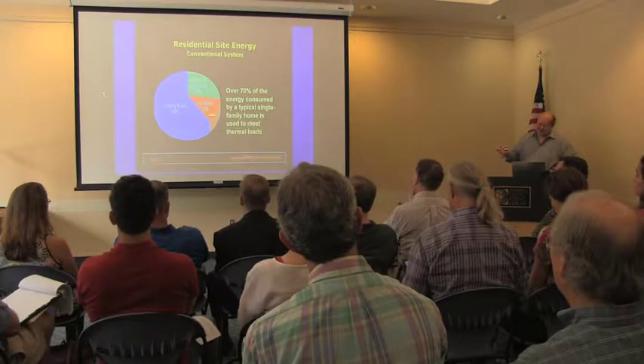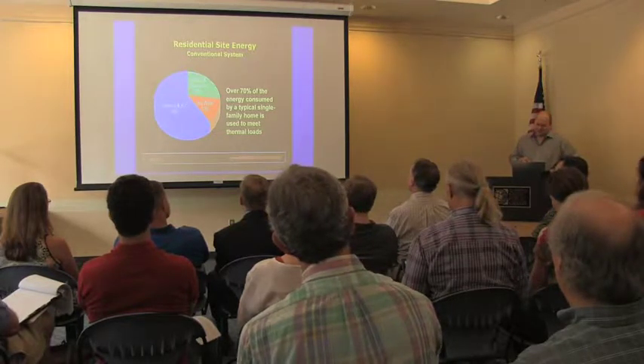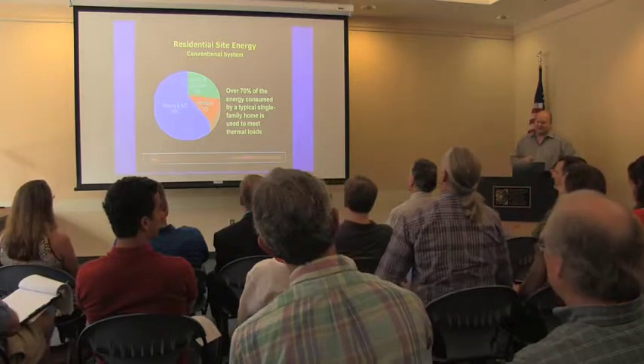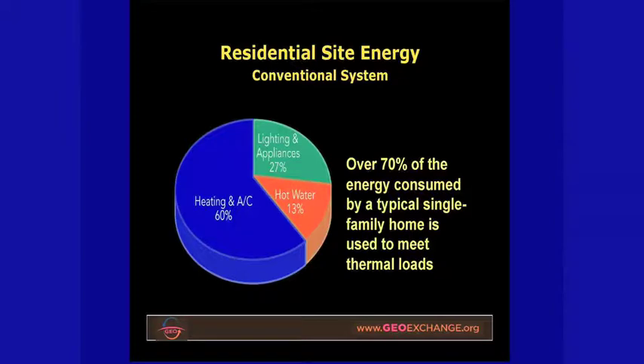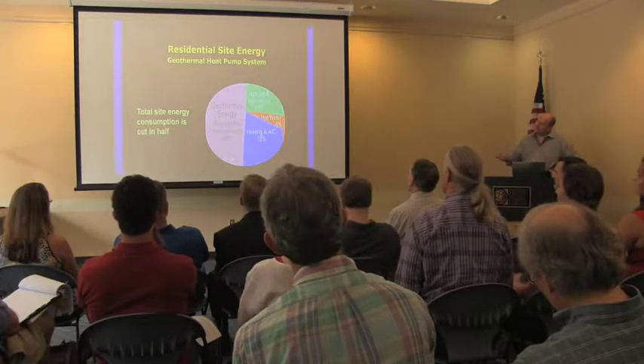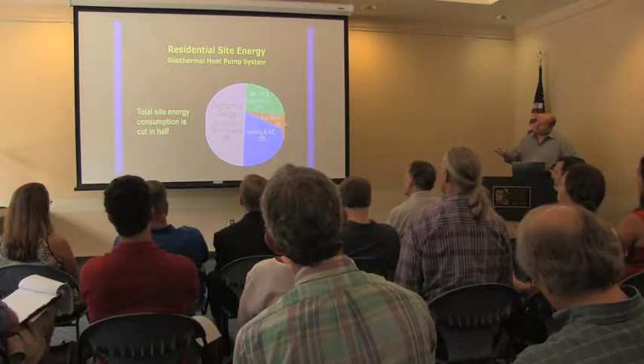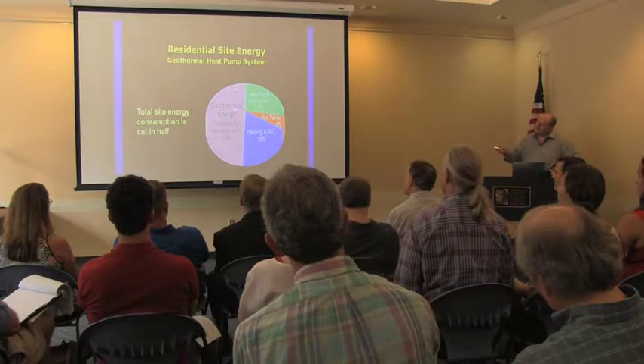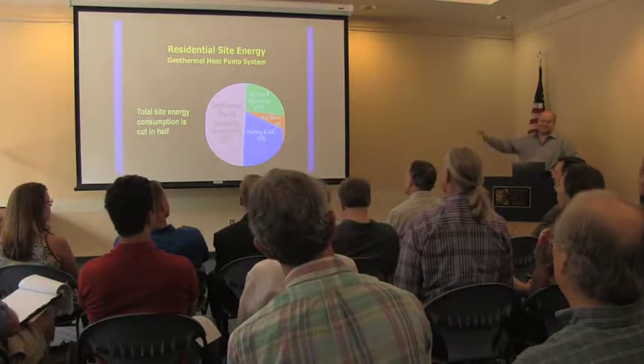So we essentially usually design our systems to make about 100 degrees of temperature coming out of the registers. I guarantee you, it heats your entire house when you're on. So this becomes important because if you understand that about 3/4 of the entire energy to heat a house goes into heating and cooling and hot water, that is a significant amount. The light bulbs and the appliances and the TVs and everything else, that's just a minor portion of it. The vast majority is the energy going into your house for heat, at least in our climate. And if you make that portion 500% efficient, then suddenly this whole thing is changing, and your hot water gets made very cheaply, and you're heating and the AC, and you can cut down about 50% of your total energy costs just by putting in a geo system. That's the entire purpose here.